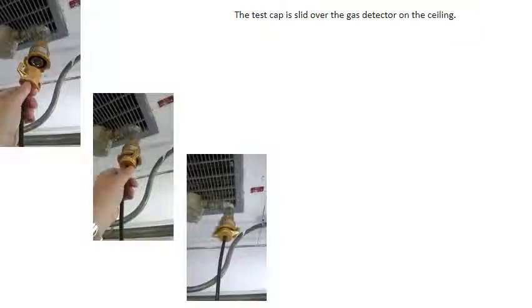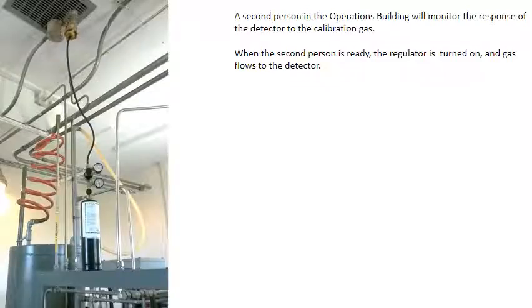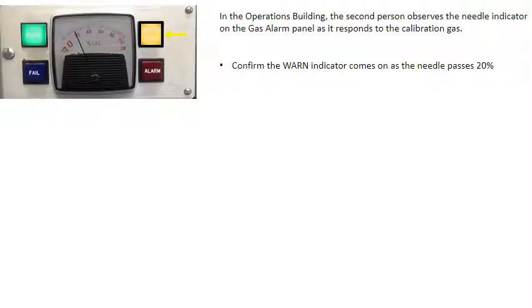The test cap is slid over the gas detector on the ceiling. A second person in the operations building will monitor the response of the detector to the calibration gas. When the second person is ready, the regulator is turned on and gas flows to the detector. In the operations building, the second person observes the needle indicator on the gas alarm panel as it responds to the calibration gas. Confirm the warn indicator comes on as the needle passes 20%.